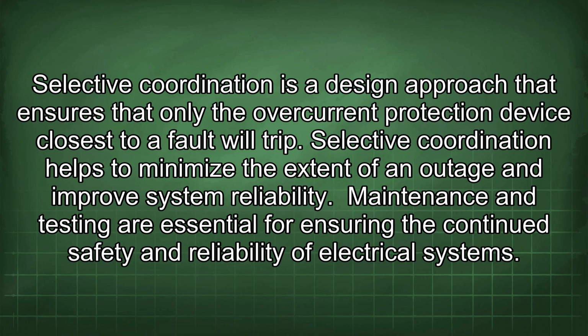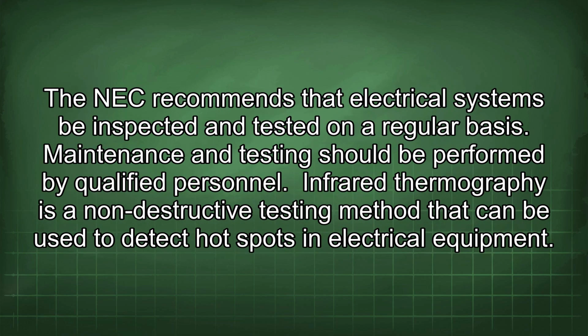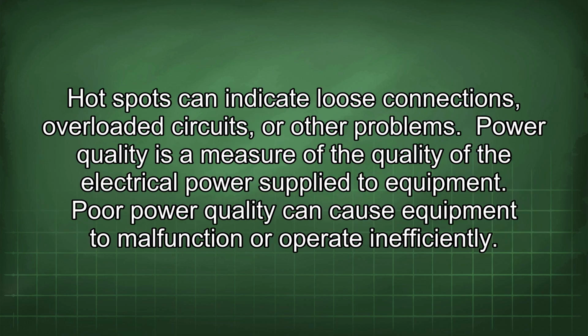Maintenance and testing are essential for ensuring the continued safety and reliability of electrical systems. The NEC recommends that electrical systems be inspected and tested on a regular basis. Maintenance and testing should be performed by qualified personnel. Infrared thermography is a non-destructive testing method that can be used to detect hotspots in electrical equipment. Hotspots can indicate loose connections, overloaded circuits, or other problems.